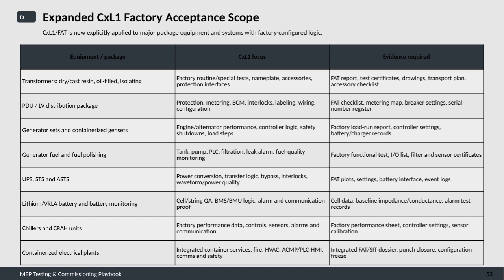Lithium and valve-regulated lead-acid batteries, along with their monitoring systems, require quality assurance on cells and strings, logic validation for battery management systems, and verification of alarms and communication protocols. Data such as cell performance, baseline impedance or conductance, and alarm test records are collected. Chillers and computer room air handling units undergo factory performance testing and controls calibration, sensor validation, alarm testing, and communication checks. The evidence includes factory performance sheets, controller settings, and sensor calibration certificates.